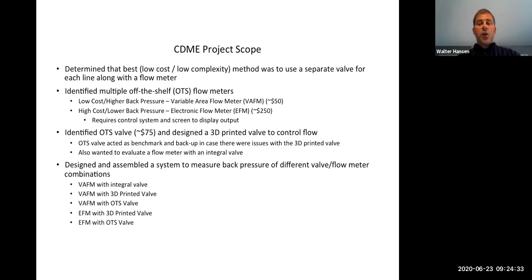So we also purchased an electronic flow meter, which is not ideal because it requires a control system, a screen, and some programming to display the flow rate, but it also creates almost no airline restriction and very little pressure drop. We also designed a 3D printed flow control valve because we wanted to enable hospitals to quickly make their own valves as needed. And we purchased an off-the-shelf valve to benchmark our 3D printed design and to make sure we had a backup in case the 3D printed design didn't work.